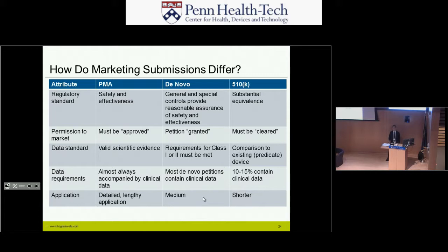Data standards and data requirements. A PMA is always going to require a clinical trial, typically a pivotal study, obviously. De novo petition or request is going to require slightly less than that, but will require a clinical trial in almost all cases. And then a 510K, about 10 to 15% have clinical data requirements, but otherwise they perform it through bench testing, animal models, cadaver models, and things of that nature.